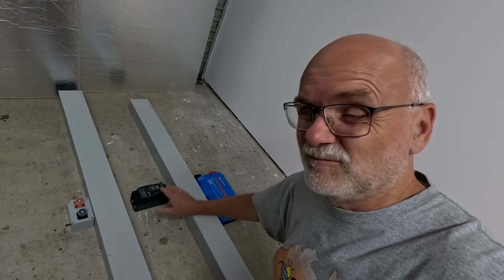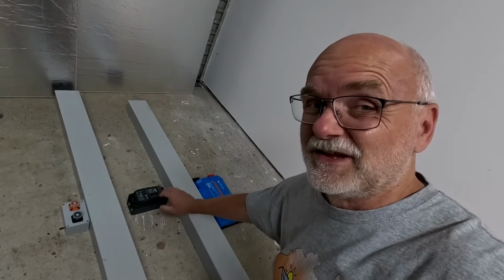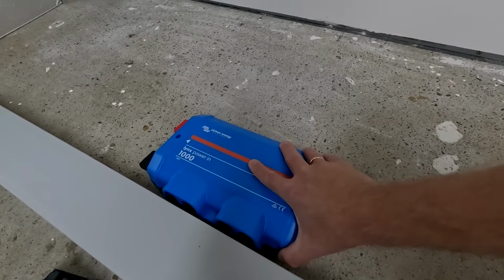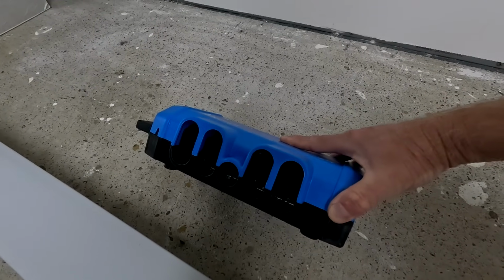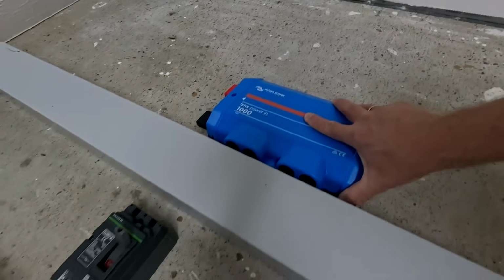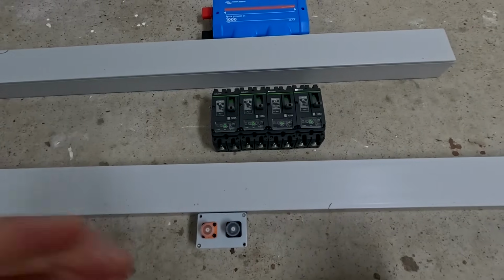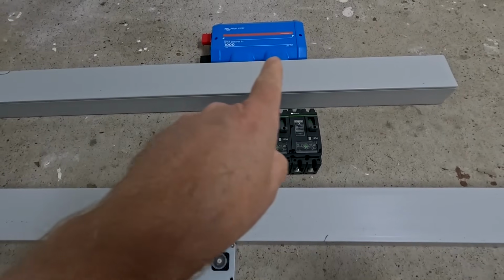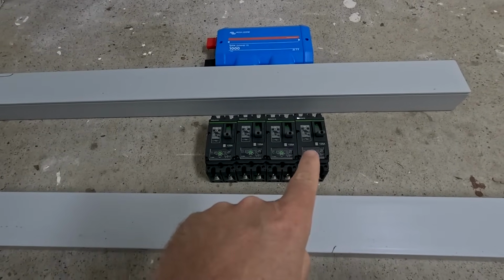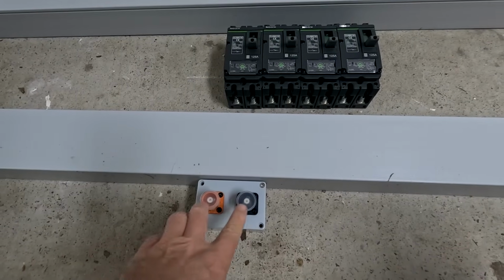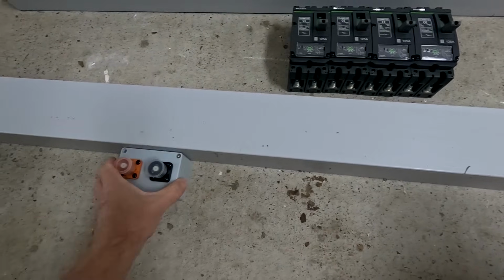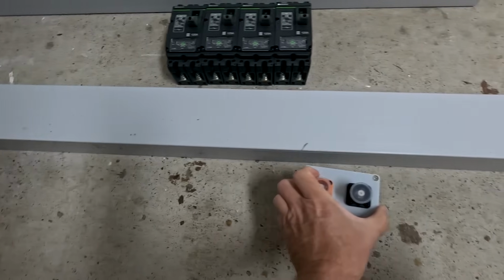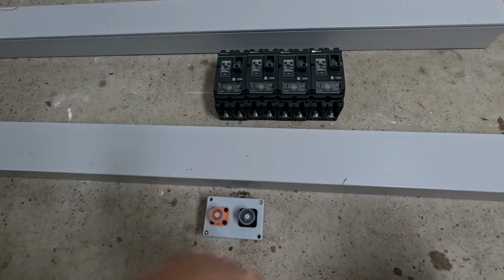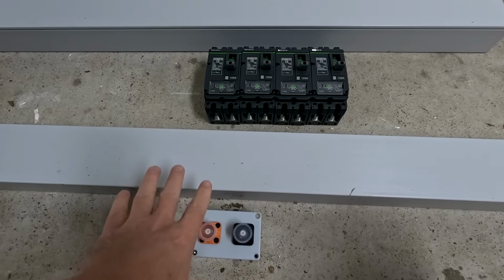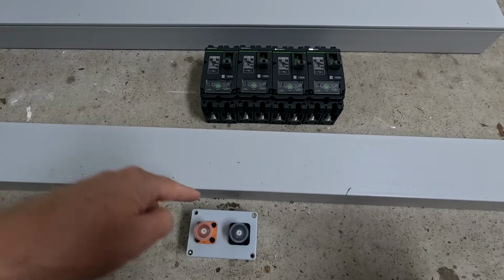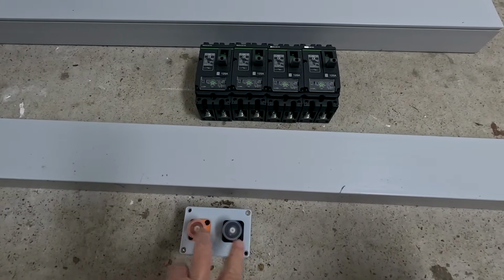Well, and obviously we don't only have one circuit breaker here, because this bus bar here not only has one battery connector, but 4 of them. So we need another. So this will be the situation then. We've got the bus bar up there, we've got 4 circuit breakers down here, and we have then 4 of these battery terminals, different locations, one over here, here, here. So a bit spread out. So I can connect 4 additional sets of batteries or even stacks of batteries to these Amphenol connectors.